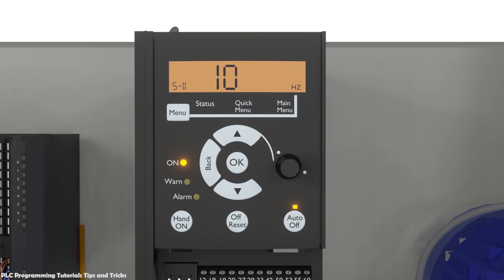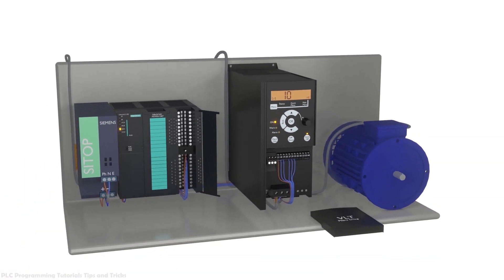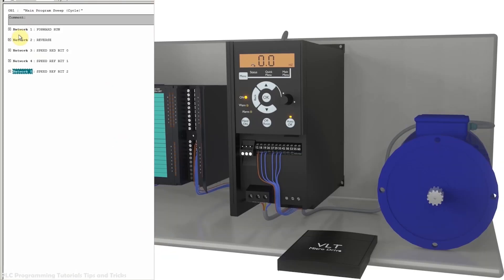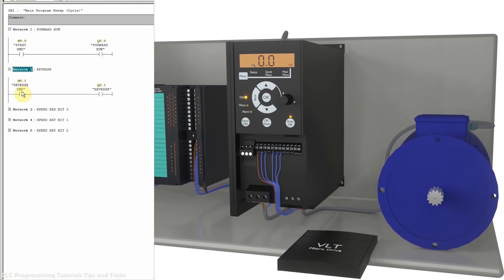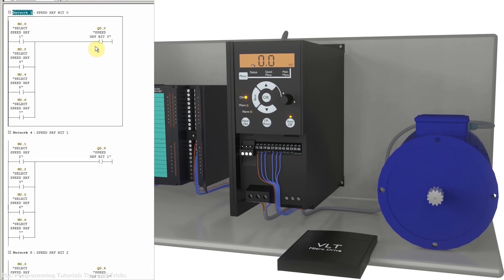Now let's go to the Simatic Manager software and discuss how the ladder logic works for this application. In network 1, when we turn on the start bit M0.0 it turns on PLC output Q0.0, activating the run command bit of the VFD. In network 2, when we turn on reverse command M0.1 it turns on Q0.1, activating the reverse command bit of the VFD. Network 3 controls speed reference bit 0, network 4 controls bit 1, and network 5 controls bit 2.